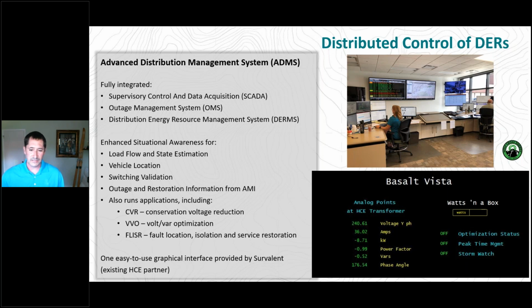What's really neat is this bottom right-hand corner. What we did was put metering at the transformer. So all 4 homes, now 9 homes that we saw in the picture on the first couple of slides, are connected to one transformer. At the transformer, we read voltage, amperage, kW, power factor, and VARs at a 1-second interval, and what we have sitting on the transformer is a coordinator.